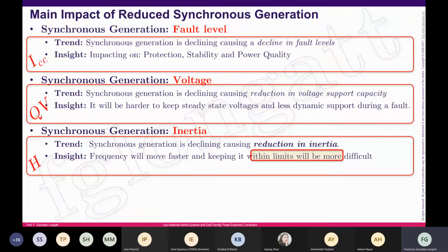Here is a very simple summary about the issues when we reduce the number of synchronous generators. The first, and extremely clear one, is a massive reduction in short circuit contribution, because power converters have limited, almost zero, capacity of producing short circuit contribution. The short circuit contribution is related with several aspects of the electrical power system, including protection: if you're using overcurrent protection, you need some level of short circuit current to identify and locate the fault condition.